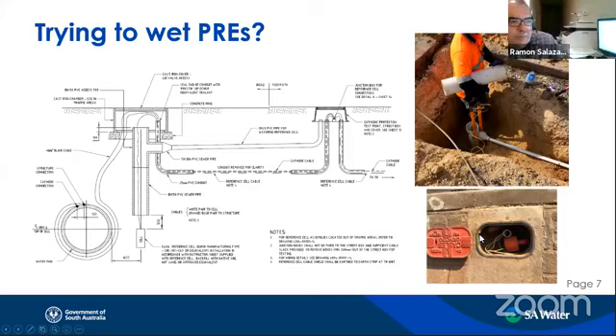One of the things is thinking about reactivating the reference electrode if it's in the middle of the road. One of the contractors did this following installation. Because the reference electrode is under the road, you have this road chamber, but you don't have access to it because you would need to set up traffic management. So they had to bring the reference electrode to the footpath. They came up with installing a PVC pipe going from the test point on the footpath to wet the reference electrode. In this photo at the bottom you see the open PVC pipe, so you pour water in and you can reactivate the reference electrode.